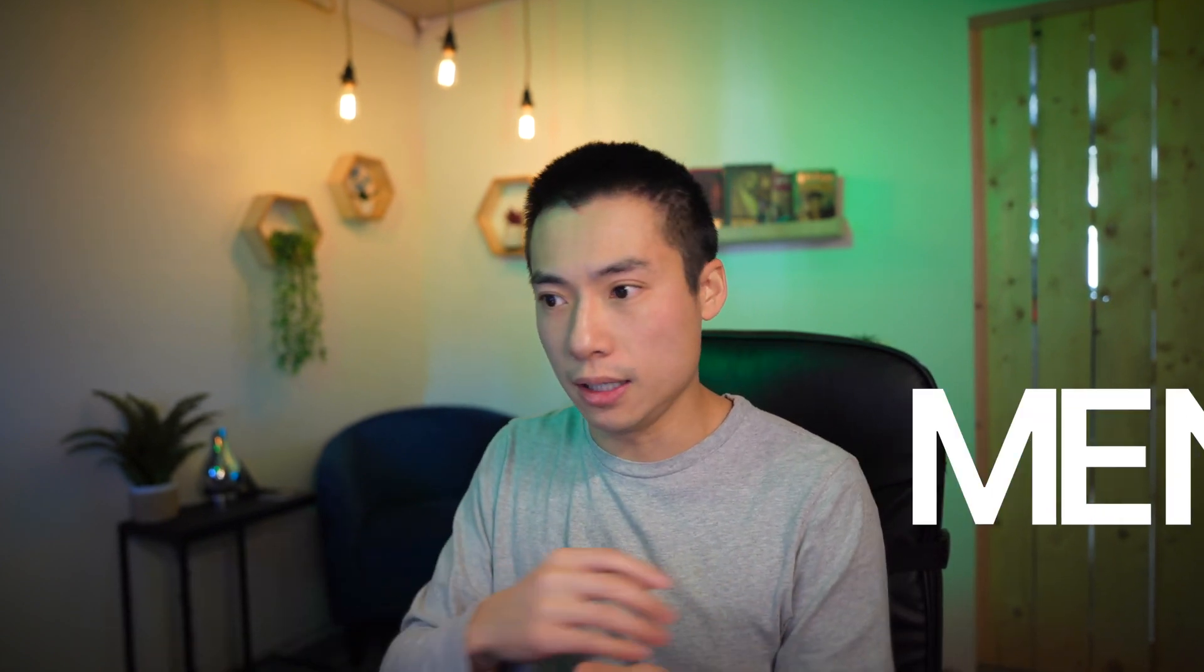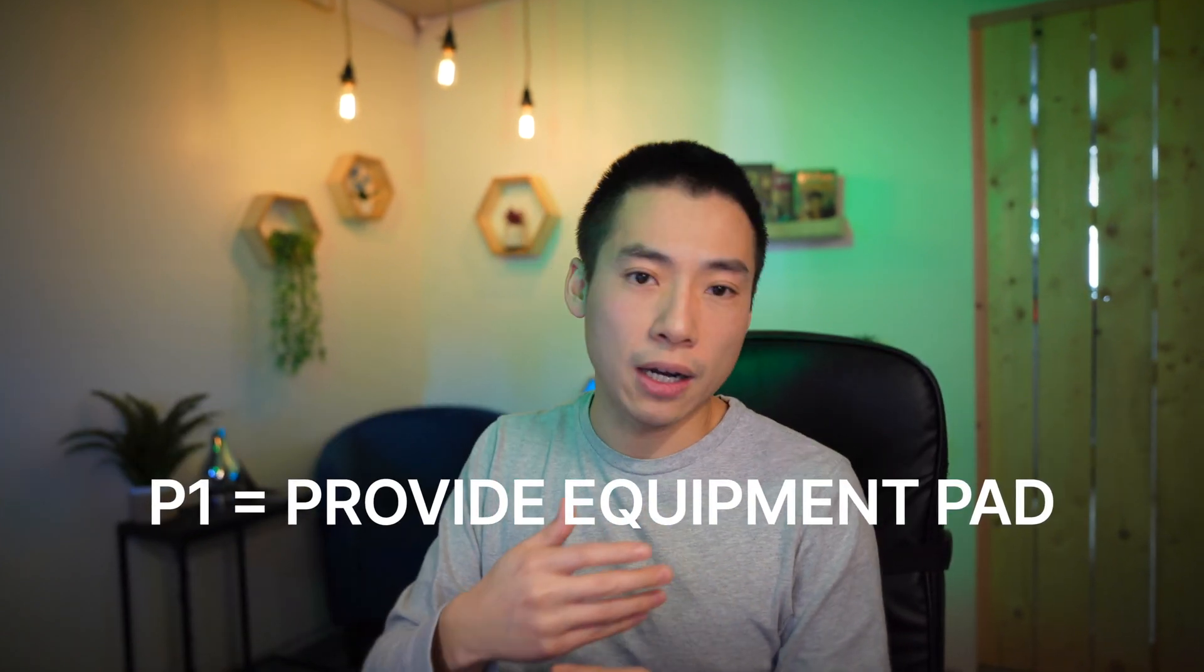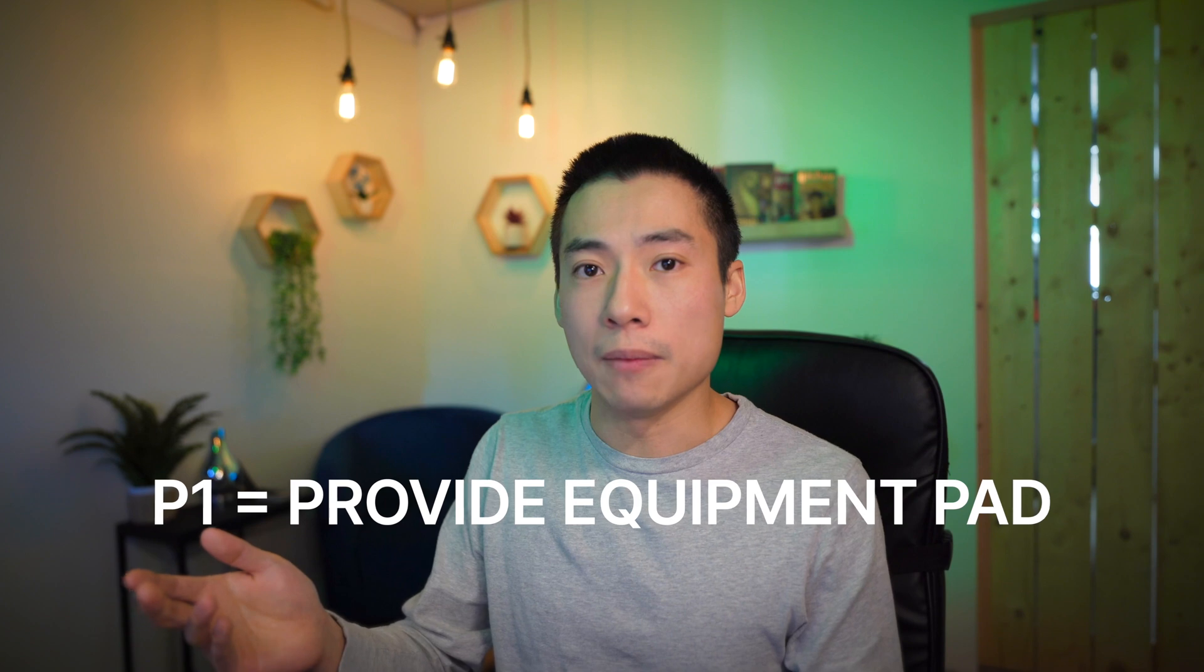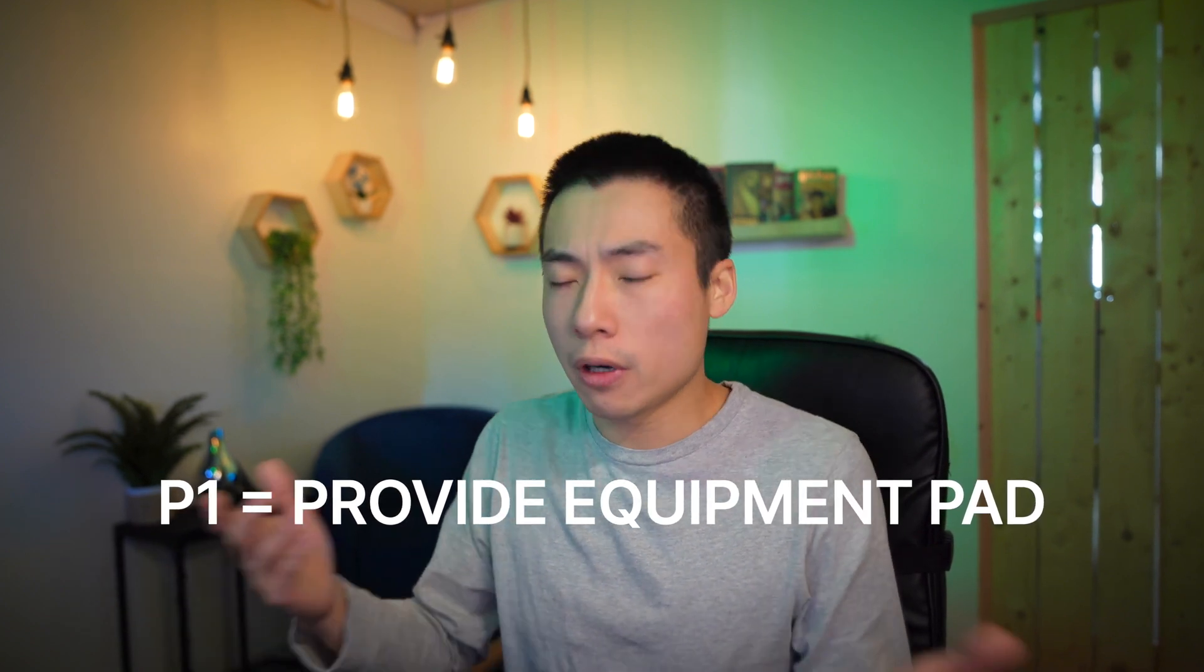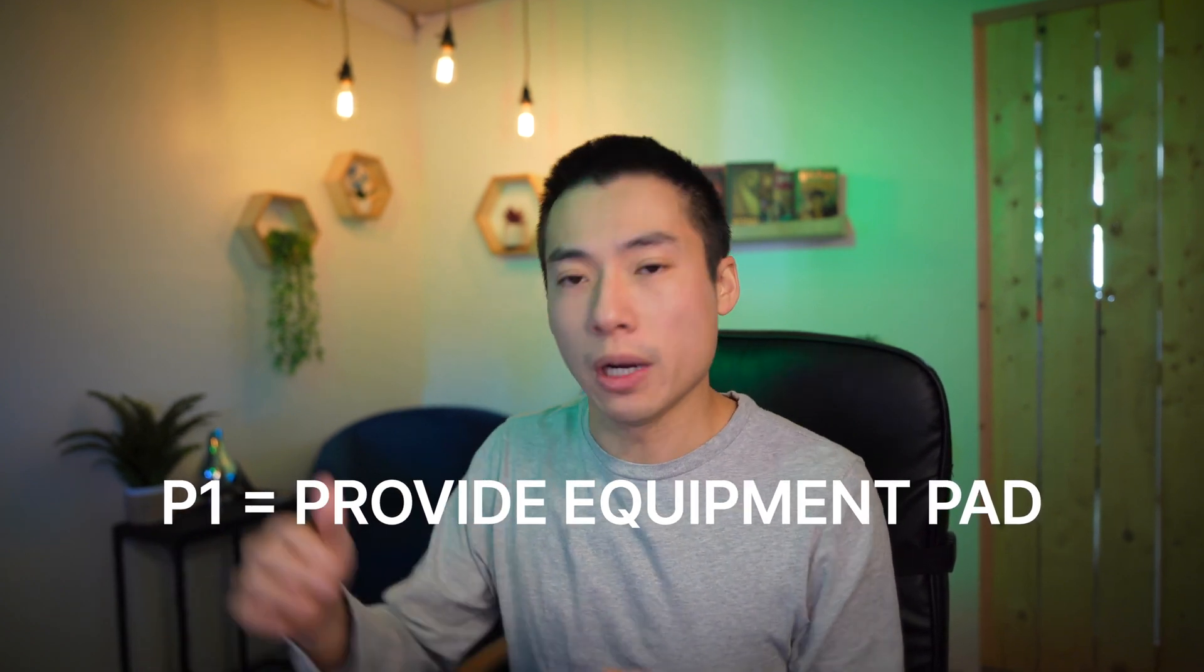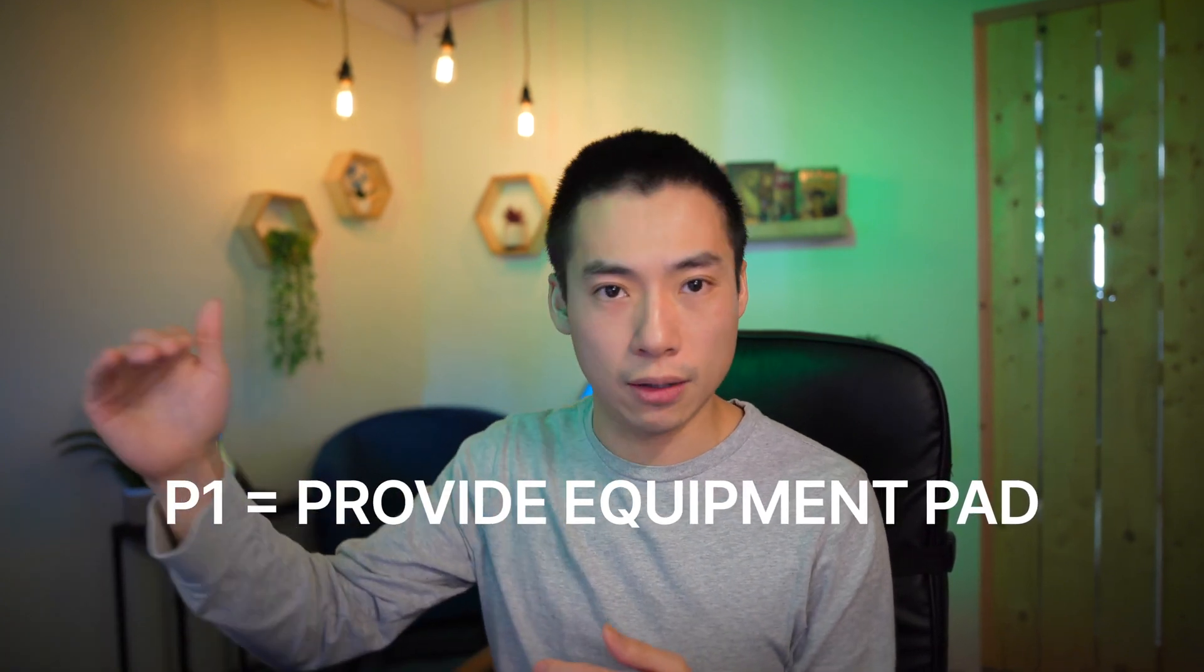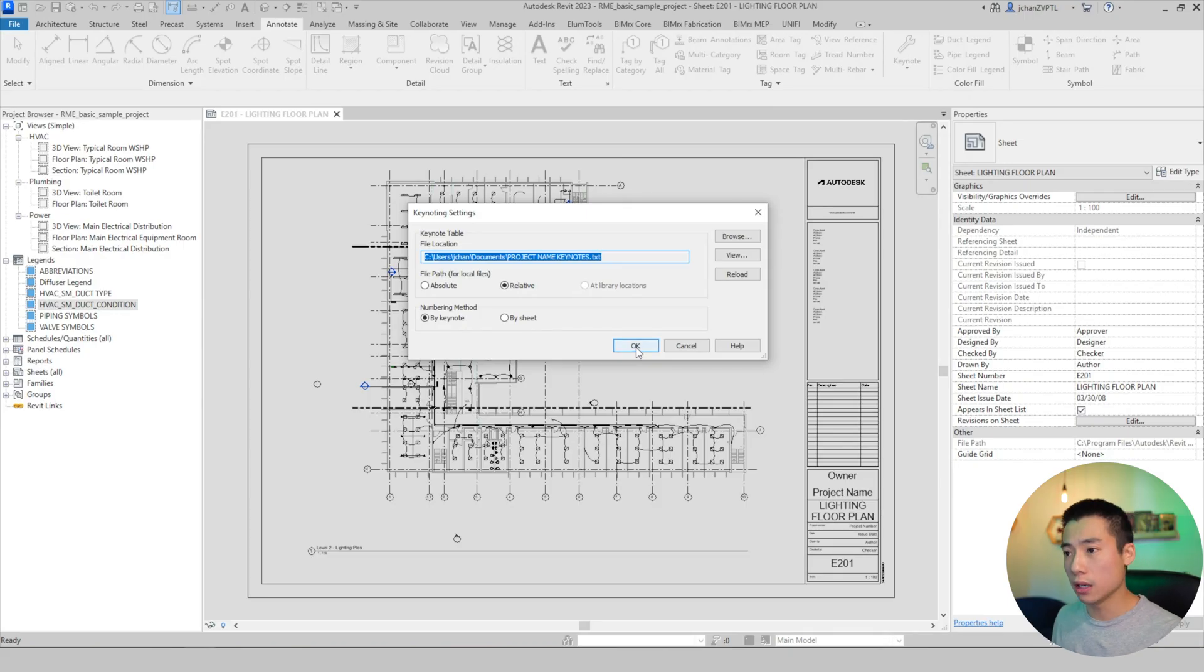If you were to renumber, if you did numbering method by sheet, then it'll all be sequential. And it will all just take whatever notes are on the drawing and do one, two, three, four, five down the right-hand side. So some people like to have it where it's like P1 all means the same everywhere. So you can say like note one is provide equipment pad and everywhere you see note one, you already know what that means. You don't have to go ahead and read the note on the side. But then sometimes on the other hand, if like having P1, P3, P7 bugs you, like if you want it to be one, two, three, and four, then you have to go by sheet. I always use by keynote. So we're just going to go ahead and stick with that. Alright. So we're done here and we're going to hit okay.